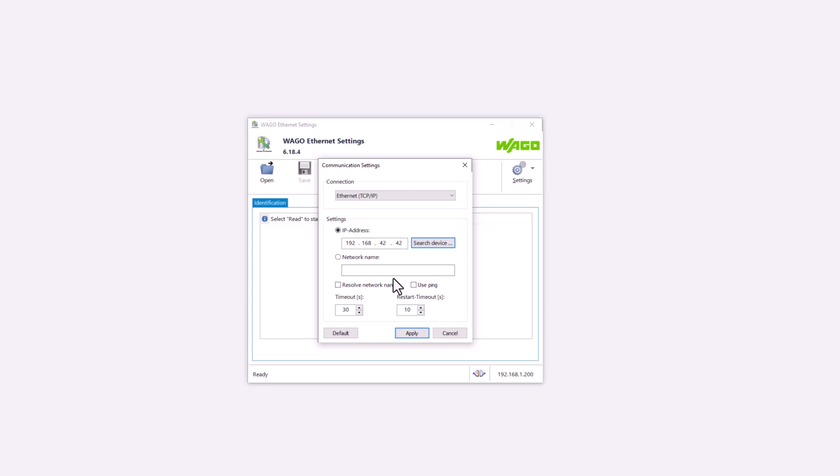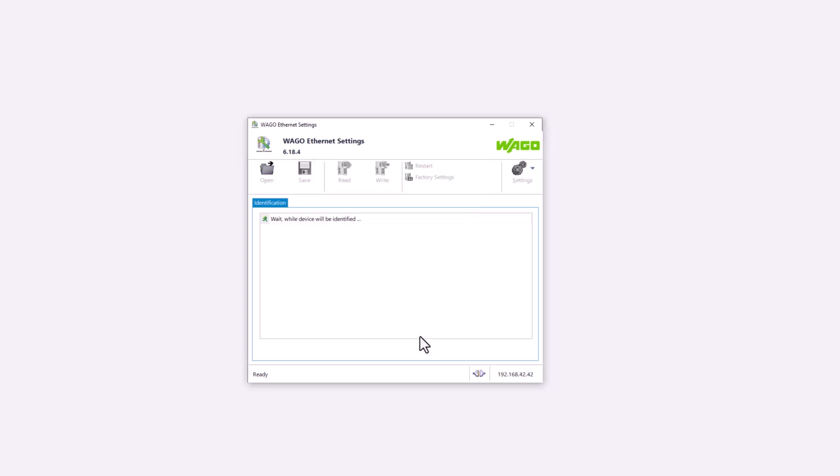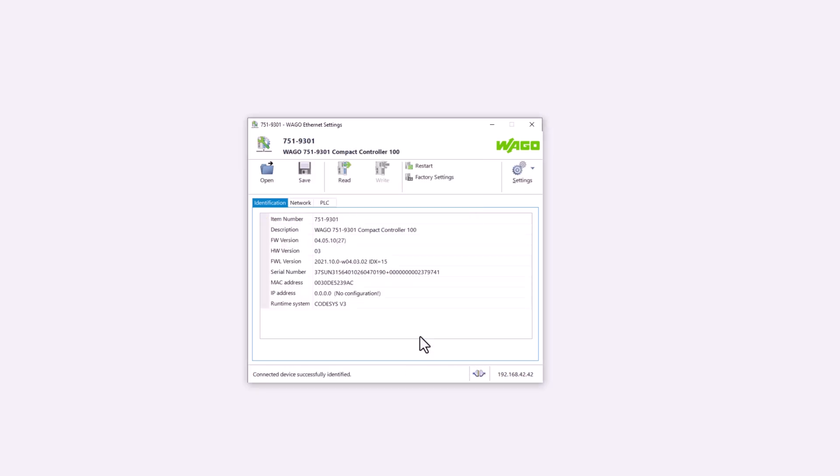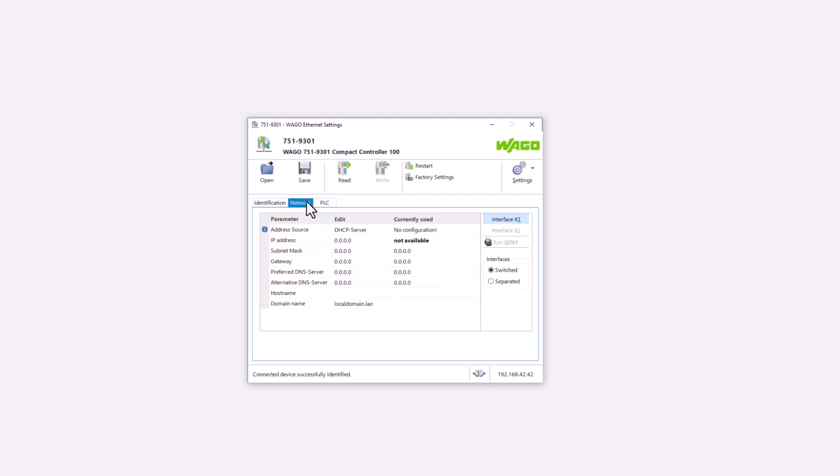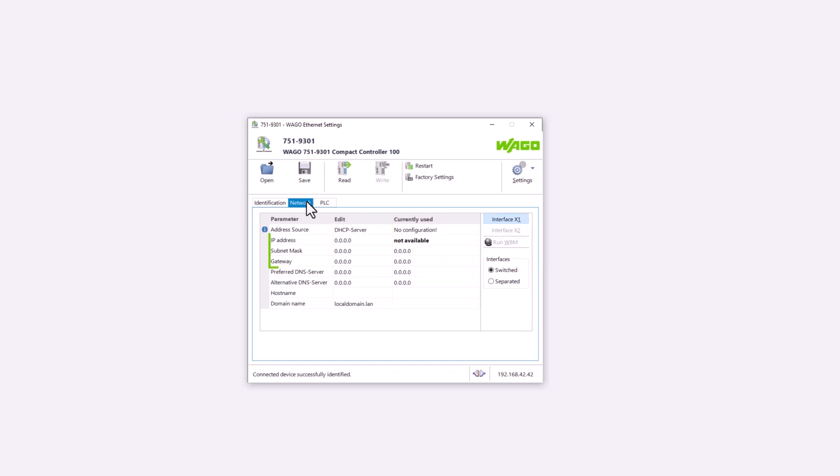A little background. The controllers with a USB service interface have a built-in USB Ethernet adapter, which means that the USB interface in the controller logs onto the PC as an Ethernet interface and we can then use it as an Ethernet interface. However, this interface can only be used as a service interface. When we apply the communication settings, the controller is detected and displayed. If we now open the network tab, we can see that the controller is set to DHCP for the switched Ethernet interfaces X1 and X2 and we could now give it a static IP address.